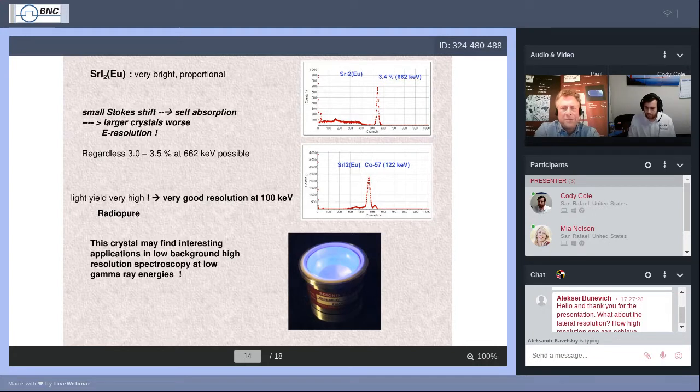All right, thank you. And I have another Eric here asking a slightly different question. I believe this was answered in chat, but are there any crystal size limitations of any of these materials compared to sodium iodide, for example? That's a very good question. The nice thing about sodium iodide, our good old classic material, is you can grow it in 400 millimeter diameter and about 400 millimeter high. This is absolutely not possible with high-resolution materials, whether you speak about LBC, cerium bromide, or CLYC or whatever.